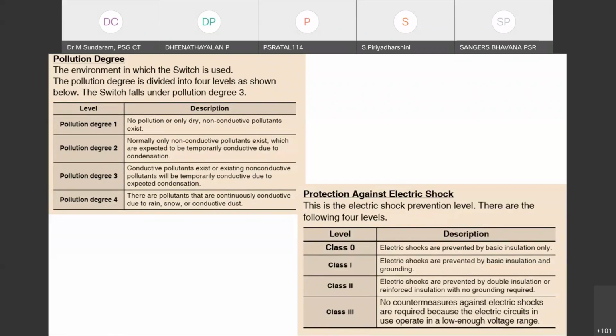Previously it was a ventilator with a pump and similar mechanisms. Now, there should not be even a milliampere of leakage current in such equipment, because it leads to a lot of issues for the human body in biomedical equipment. That's why this is most important.